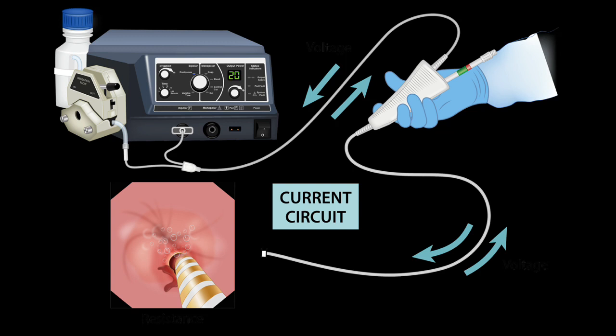So we've learned about how to set up a monopolar device, which is most commonly used in every endoscopy unit every day. And we also talked about bipolar device, especially for bleeding ulcers or for Barrett's esophagus. The difference between the two is that for bipolar, you don't need a dispersive pad. And remember, when it comes to the dispersive pad, you have to be very careful in applying it close to the site on a big mass of muscle, away from bony points, away from tattoos, away from the hairy areas, away from any medicinal gels applied to the skin.